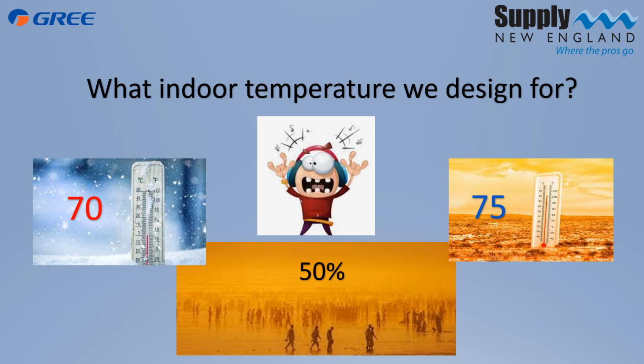Now remember, an oversized system will cool so quickly that it will not dehumidify, so it's going to be cold and clammy. Even at 68 degrees, we may still have 60% humidity, and that doesn't feel very good. An undersized system is going to make a great dehumidification system, but not a very good air conditioning system. And that's why proper sizing is key.